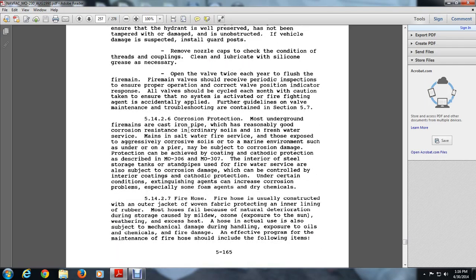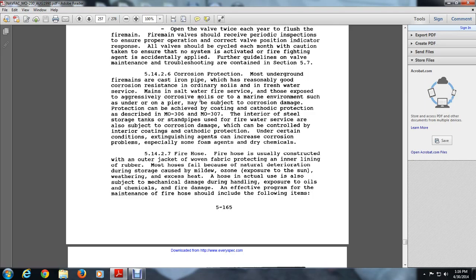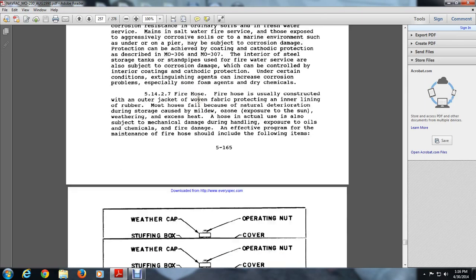5.14.2.7 Fire hose. The fire hose is usually constructed with an outer jacket of woven fabric protecting an inner lining of rubber. Most hoses deteriorate naturally during storage, through mildew, ozone, exposure to the sun, weathering, and excessive heat. A hose in actual use is also subject to mechanical damage, handling, exposure to oils, chemicals, and fire damage. An effective maintenance program for fire hoses includes the following.